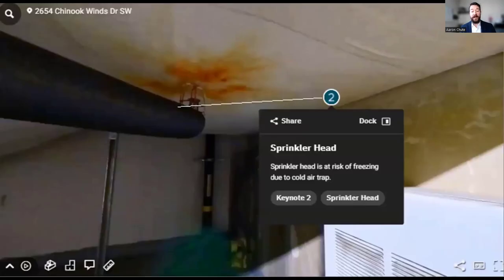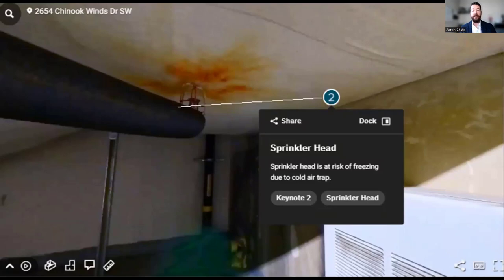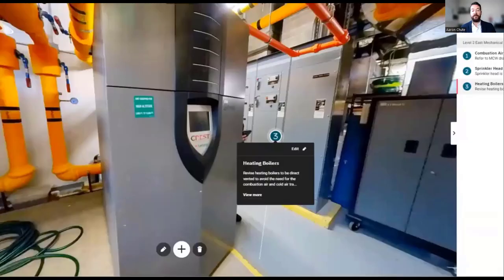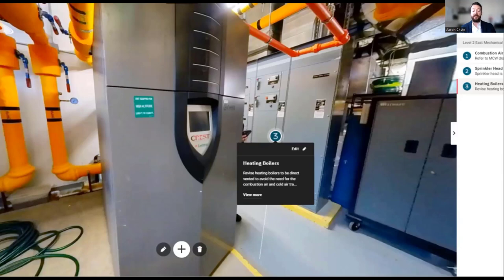Here's the sprinkler head that froze on a beautiful minus 35 day in Alberta. This is the virtual tag we added to show the bidding contractor the problem and why it needed to be revised. Any smartphone can simply hold up its camera, read the QR code, and you're transported right into the site — no passwords, no apps to download. It's all web-based. We embedded those drawing keynotes directly onto the model so the contractor can check orientations and produce a much more accurate bid price. The reason for the outdoor air duct is that the boiler burns natural gas and requires air to burn.